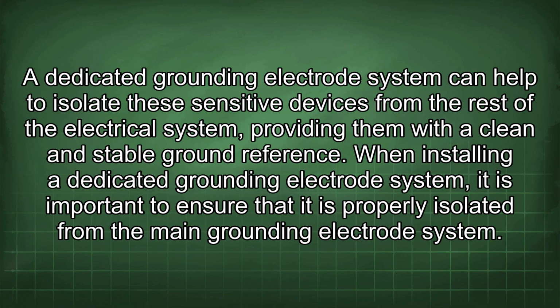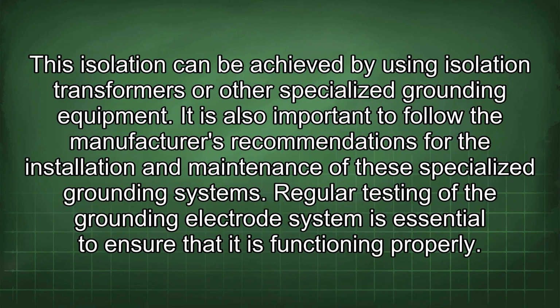A dedicated grounding electrode system can help to isolate these sensitive devices from the rest of the electrical system, providing them with a clean and stable ground reference. When installing a dedicated grounding electrode system, it is important to ensure that it is properly isolated from the main grounding electrode system. This isolation can be achieved by using isolation transformers or other specialized grounding equipment. It is also important to follow the manufacturer's recommendations for the installation and maintenance of these specialized grounding systems.